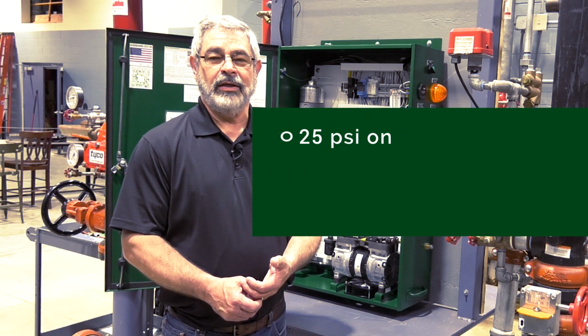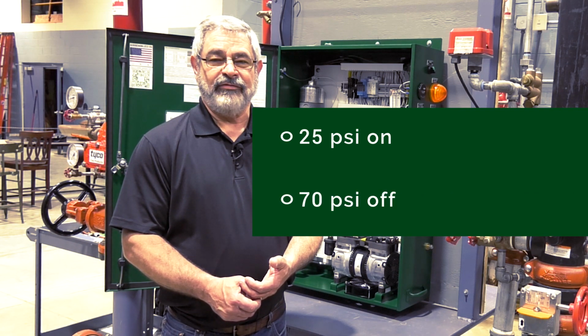In this project, the operating pressure is 30 PSI. With that being said, and checking that our low air alarm is coming in at 20, we're going to program the nitrogen generator to turn on at 25 PSI. The turn off pressure needs to be approximately 40 PSI above the air maintenance device or the supervisory gas operating pressure. So in this application, we're going to adjust our nitrogen generator to operate at 25 PSI on and 70 PSI off.